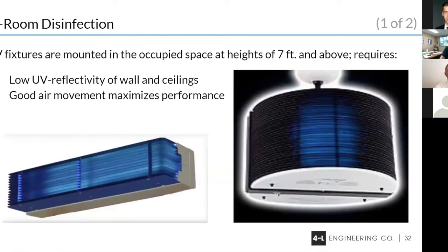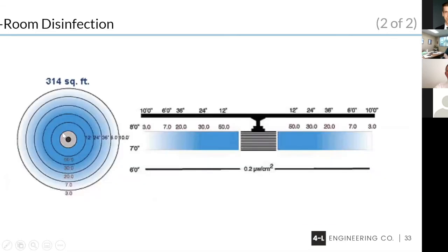We can also put UV lighting inside the room, usually at a 7-foot height, and we'll put it around the perimeter of the room, or in a covered area that may surround the room, or you can hang it directly from the center of the room. Remember that UV lighting should not be looked at directly with your eyes because it will affect them. So we have in-room disinfection. This is the area that the center light covers around the circumference. Next slide. It goes 10 feet out all the way around in a radius.